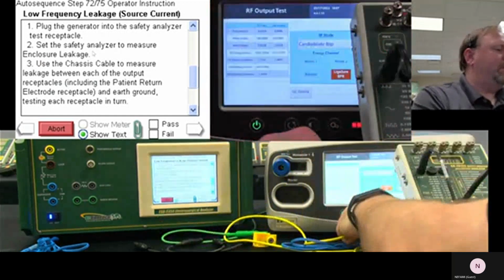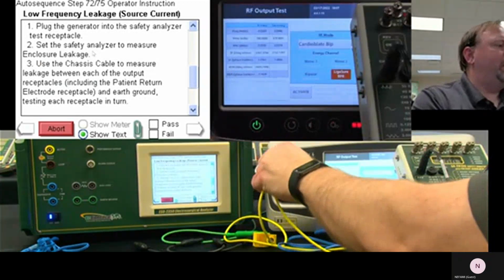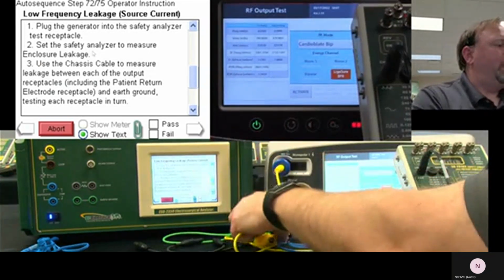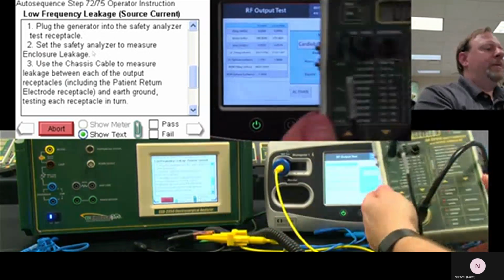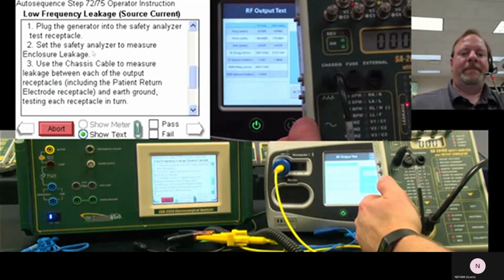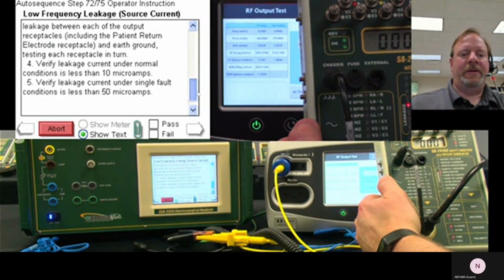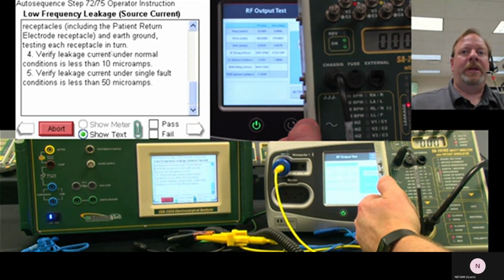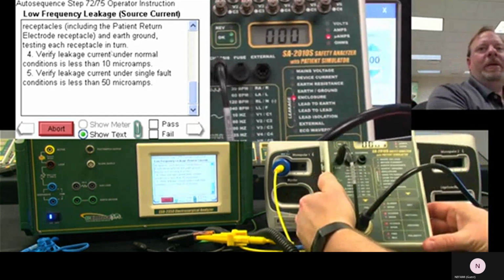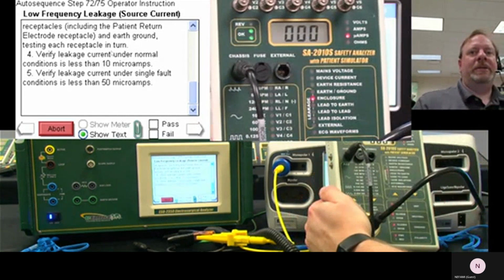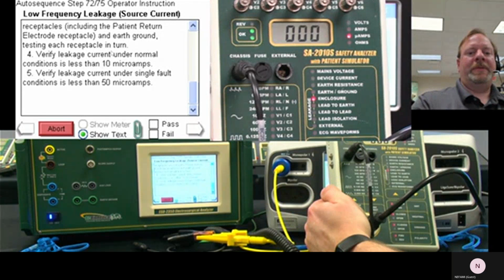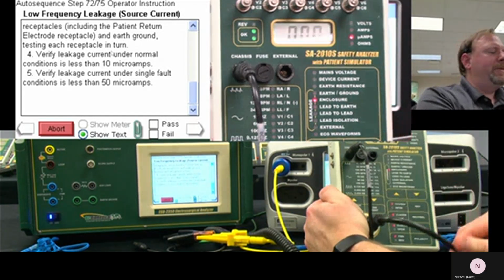We'll just connect to all of these one at a time. And measurement. So our instructions here are: verify that under normal conditions we have under 10 microamps, and under single fault we have under 50 microamps.